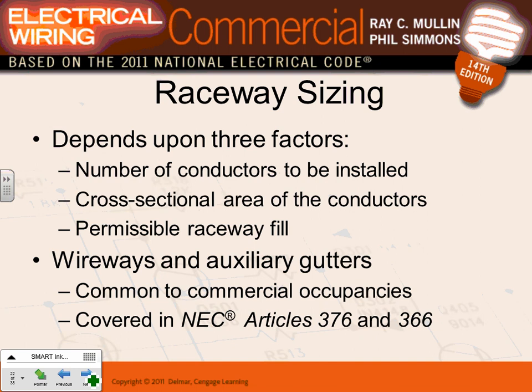Conduit support: typically we support rigid conduit and EMT every 10 feet, and within three feet of every box. They have different support requirements depending on size. Raceway sizes depend on how many conductors you put in a raceway, the cross-section of the raceway, and the insulation type. We'll do an example: take a bunch of conductors and size a raceway for them. Three things when sizing: the size of the conductor and its insulation, and the type of conduit needed - EMT, PVC, or flexible.